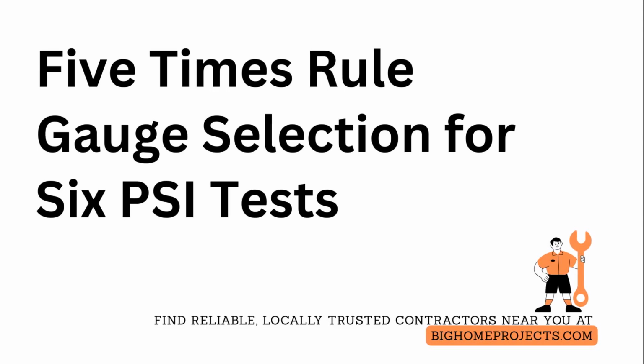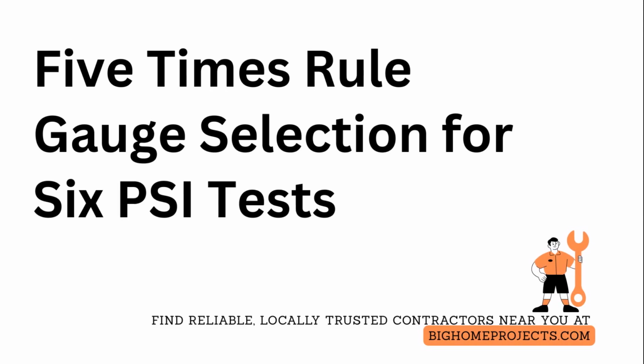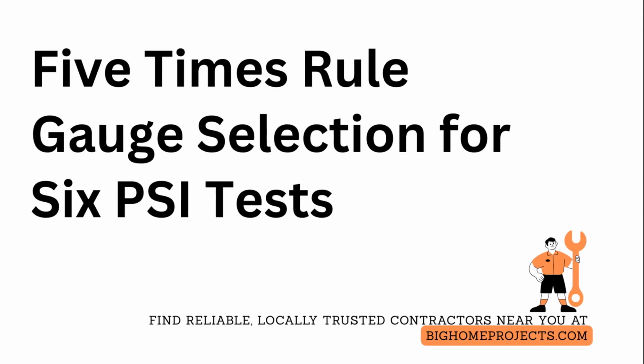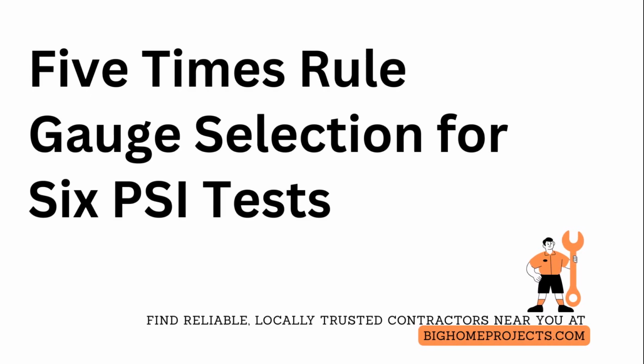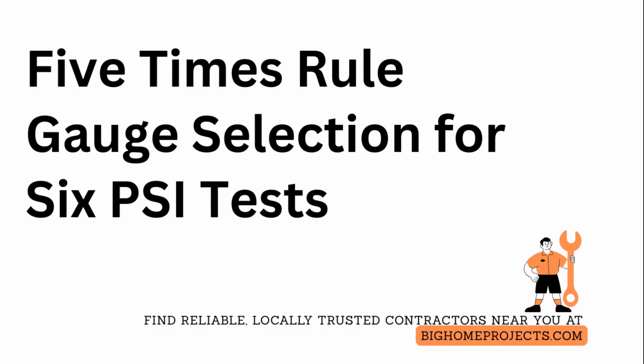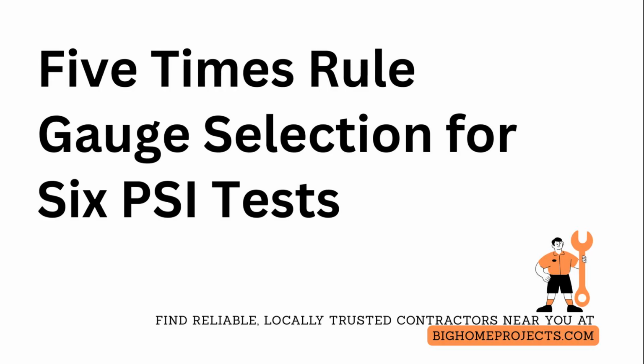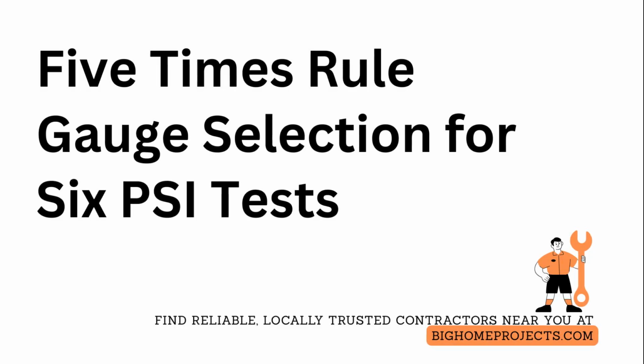Pressure testing gas lines requires using a pressure gauge whose full-scale range is appropriate to the test pressure so you can detect small leaks without overloading the instrument. For a 6 pound per square inch test, choose a gauge with a range that gives at least 5 times the test pressure on the full-scale rating so the needle does not peg, and the calibration remains accurate.